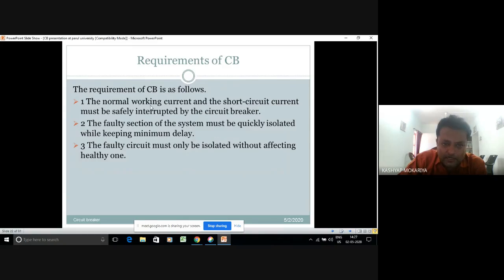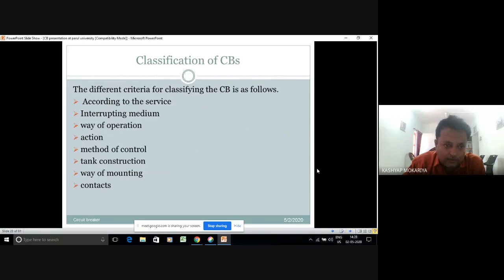So the requirement of a CB is that the normal working current and the short circuit current must be safely interrupted by the breaker. The faulty section of the system must be quickly isolated while keeping minimum delay. The faulty circuit must also be isolated without affecting the healthy one. So these are the points.